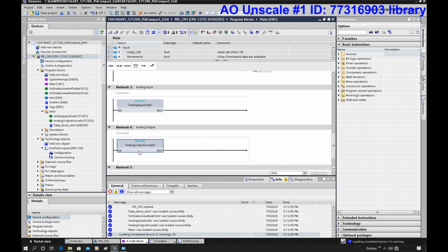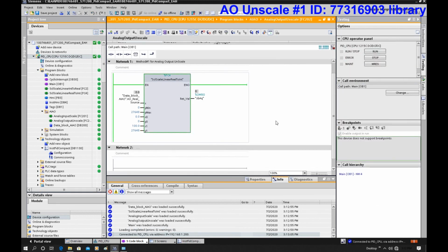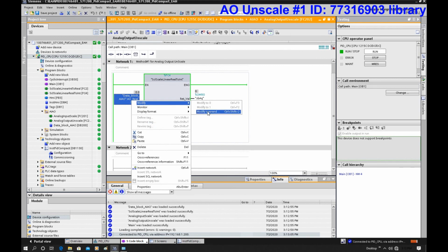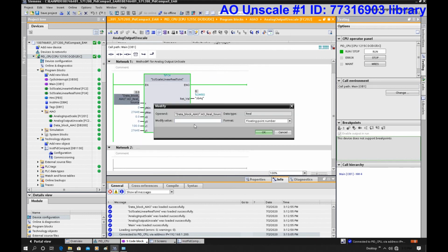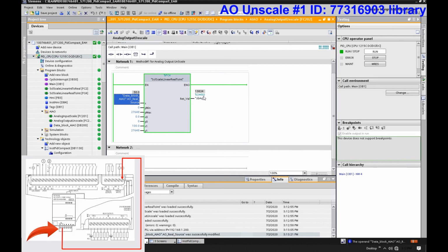Okay, let's double click, hit the online monitoring. Okay, currently that is 0. Let's type in 50, modify this setting. 50%. Okay, 50. So it got an output. Firstly, let me measure the output using the multimeter. Okay, the output shows 4.98, almost 5 volts. Okay, that's fine.